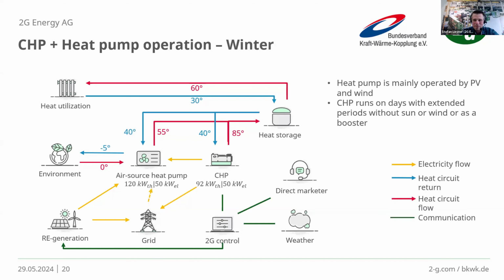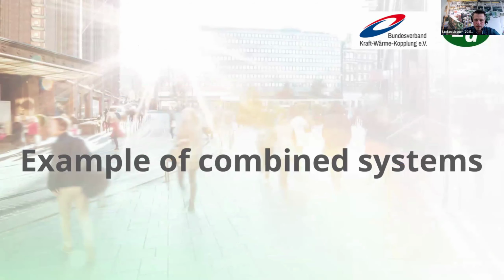And then the extreme example in winter, when you have only 0 degrees outside ambient temperature, then of course the CHP has its strength as a kind of booster, having longer operating hours in winter. And if you compare the total power of the heat pump, you see that here the total power of the heat pump is only 120 kW thermal. Only an example, but just to show the thermal power development of these heat pumps in winter. I know that the other two guys will also have some examples.